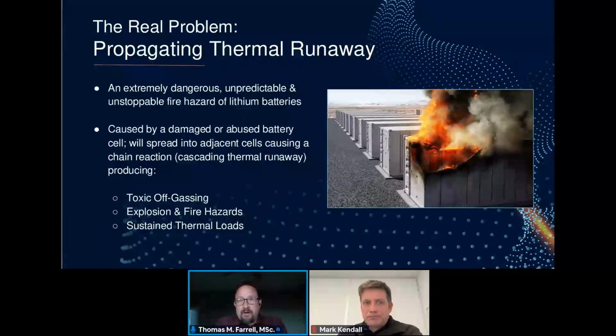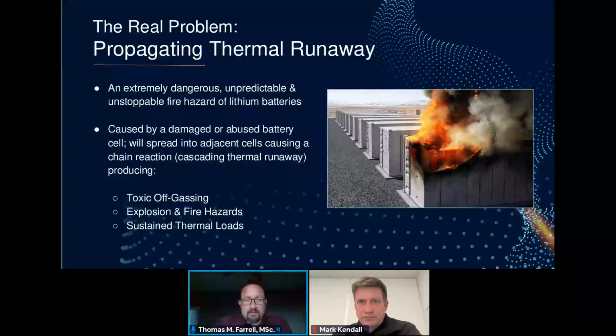But was that the actual problem we were dealing with, and was that the actual hazard? The real problem in these scenarios is propagating thermal runaway. That is an extremely dangerous, somewhat predictable, but it can be unpredictable process depending on electrical configurations. It's a process where one cell propagates to another cell, until you have enough heat in a module that it propagates to another module. And then that can involve an entire pack, and move throughout an entire rack.